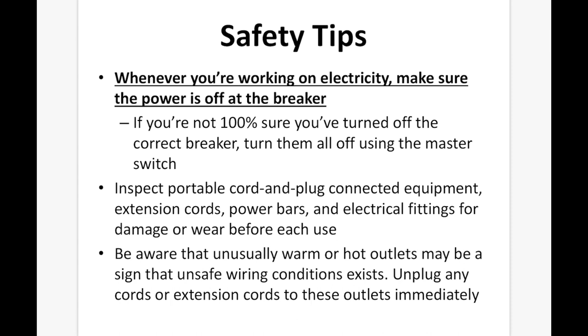Do not touch a person or electrical apparatus in the event of an electrical accident. Always disconnect the power source first. Watch out for nearby hazards, power lines, water, or metal objects around the victim that may be carrying current. Do not plug high amperage equipment such as space heaters, portable air conditioners, and other power equipment into extension cords. They should be plugged directly into working receptacles only.